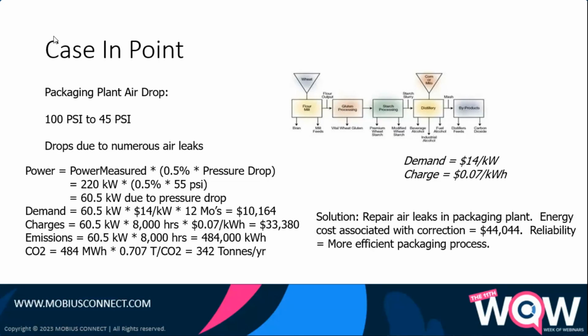That comes out, if I use $14 per kilowatt and 7 cents per kilowatt hour, and 8,000 hours of consistent use, and mind you, there's some variability, but this was always considered conservative, that would be $33,380 in just energy, $10,164 in demand charges, which is a significant amount. That's $44,000 just feeding air leaks in the system.